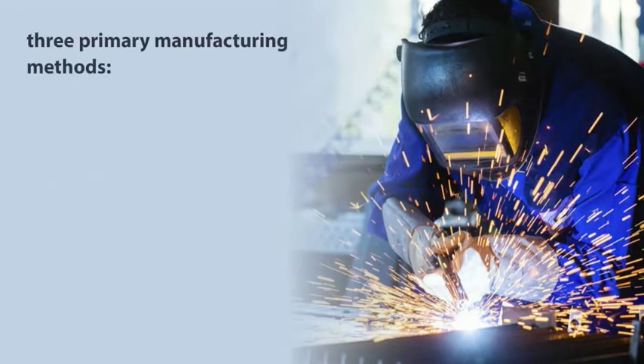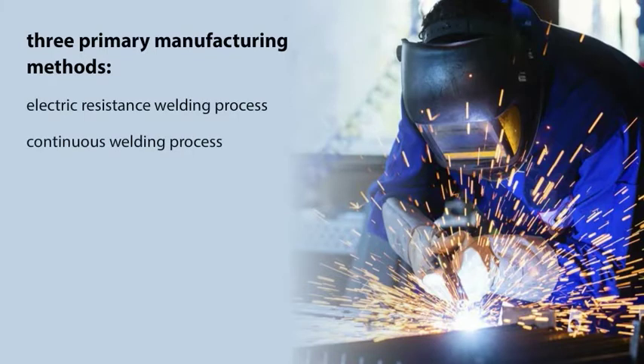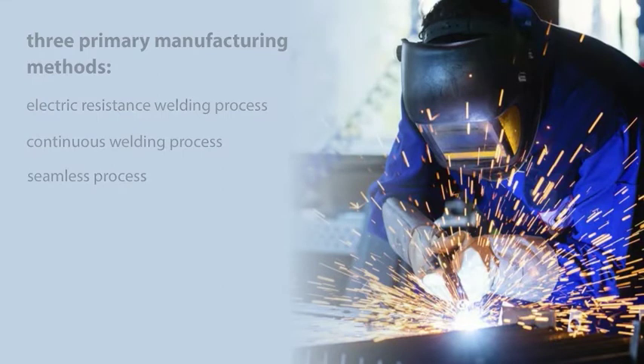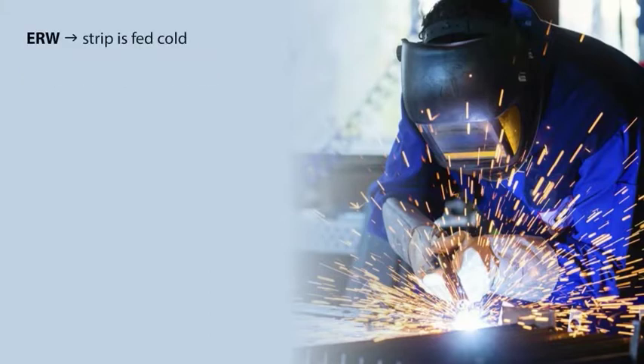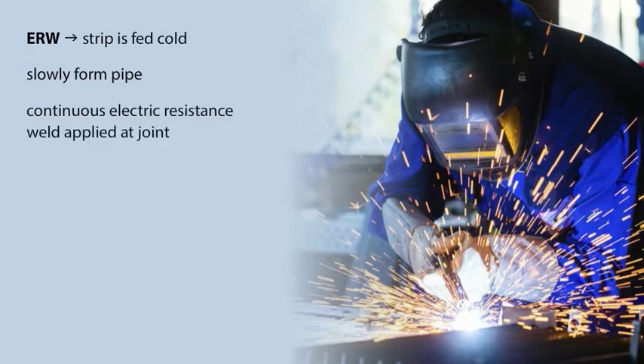There are three primary manufacturing methods for steel pipe: the electric resistance welding process, the continuous welding process, and the seamless process. In the ERW process, the strip is fed cold and unheated toward rolls that slowly form the pipe into an oval and then a precision cylinder, and a continuous electric resistance weld is applied at the joint.